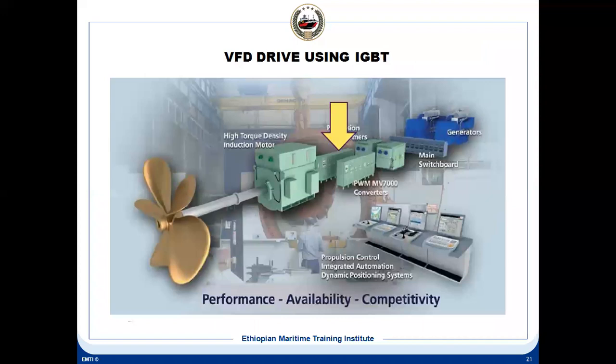I told you the advantages are, it is energy saving. The main thing is energy saving. Low motor starting current, reduction in thermal and mechanical stresses, simple installation, high power factor, low kVA. Onboard ship, in addition to the propulsion on the passenger ship, you'll also find it in centralized cooling systems. In these centralized cooling systems, the motor is always running.